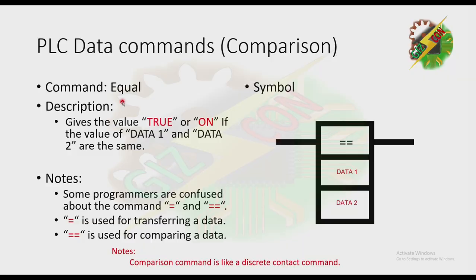Now we have the Comparison commands. First is Equal — it gives the value true or ON if the value of Data 1 and Data 2 are the same. Take note: some programmers are confused about equal (=) and double equal (==). Equal is used for transferring data, while double equal is used for comparing data. Note that a comparison command works like a discrete command. This is the symbol for this command.